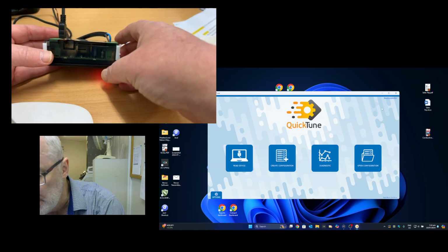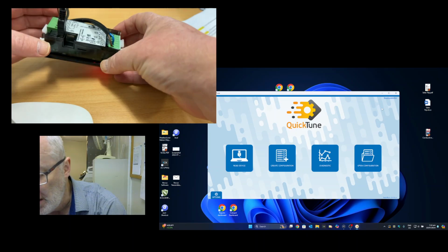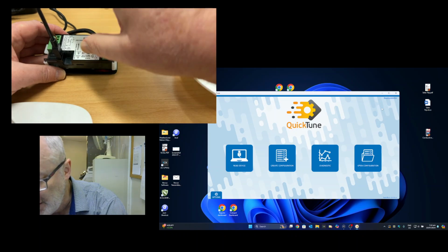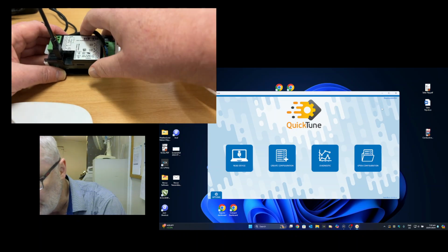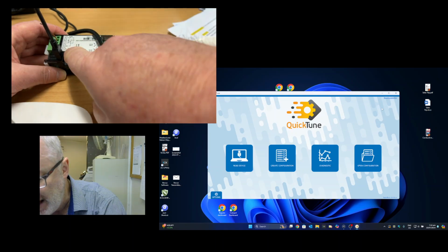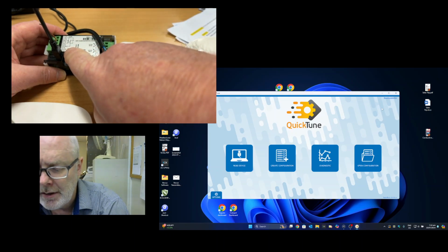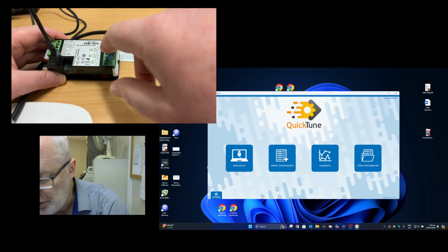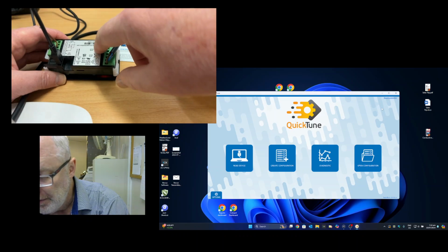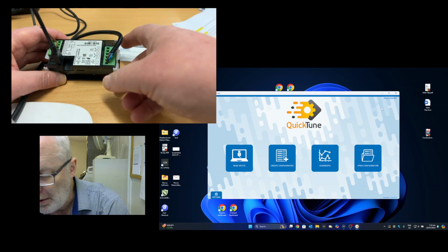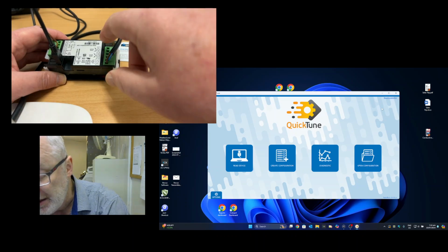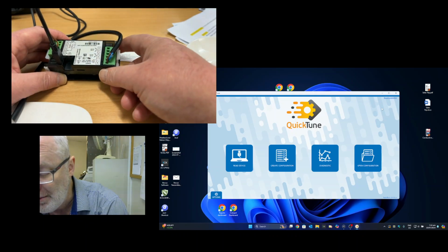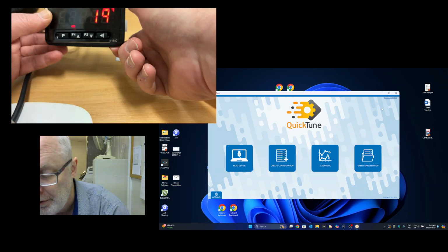nominally 24 volts. It has a universal input, so we can put in thermocouples, RTDs, milliamps, etc., ad infinitum. And we have a 24 volt out to power other devices such as a transmitter. But also we have two relays. So it's almost a basic controller as well. We can set two points that could be driven from the alarm outputs, of which there are two.